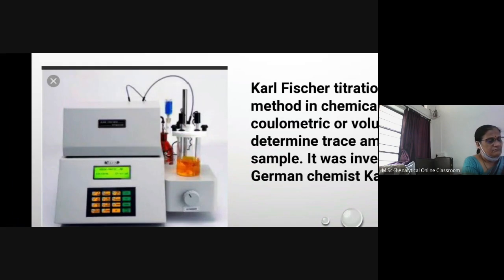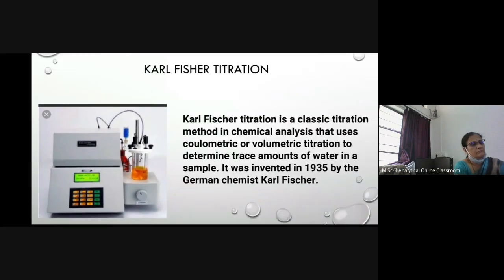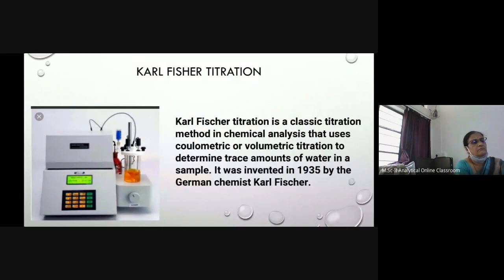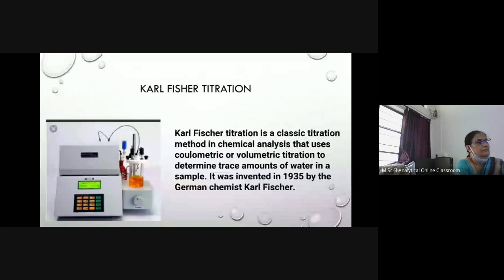First of all we have to determine the factor of this machine per day, and after that we insert our sample in very small amounts, like milligram or microgram. When it is started, it pumps the iodine in milliliter amounts, and when all the water molecules are consumed, it shows us the endpoint, which is further used in calculation to find the percentage of water present in our sample. This machine is very useful in industries.